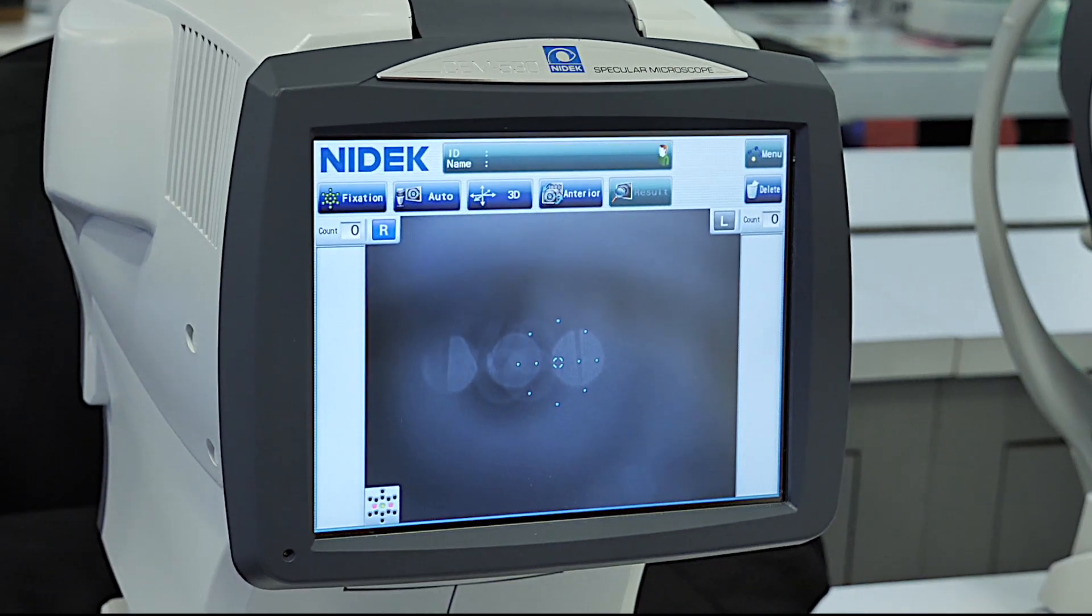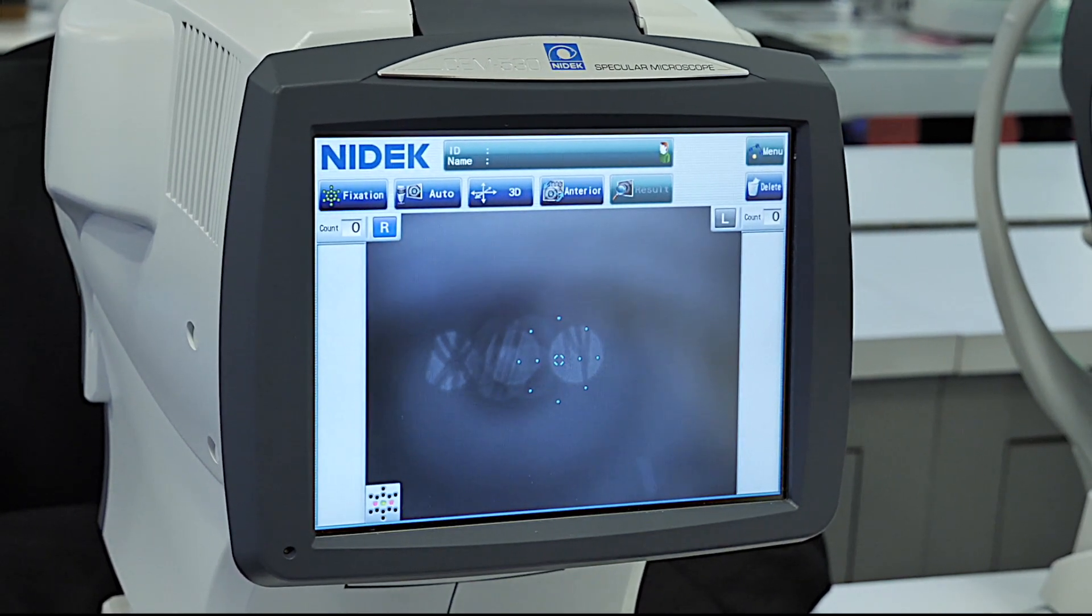Here we have the NIDEK CEM-530 Specular Microscope to evaluate the endothelium of patient's corneas. It's important to evaluate the endothelium prior to any anterior segment surgery or if you're fitting patients with contact lenses. I'm going to give you a quick demo of the CEM-530 Specular Microscope by NIDEK.